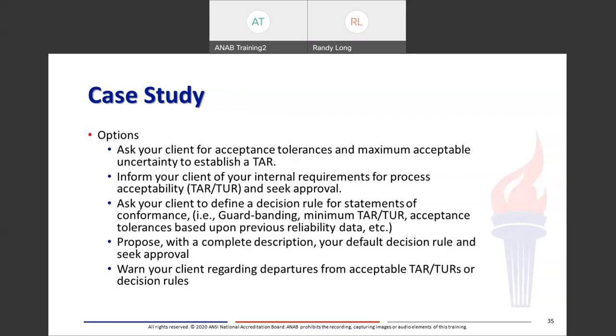Options: a calibration laboratory can ask a client for acceptance tolerance and maximum acceptable uncertainty to establish a test accuracy ratio. The laboratory could inform the client of internal requirements for process acceptability and seek the customer's approval. A calibration laboratory can ask the client to define a decision rule for statements of conformance — for instance, guard banding, minimum TAR, or acceptance tolerance based on previous reliability data. You should propose with a complete description your default decision rule and seek approval, and also warn your clients regarding departures from acceptable TARs, TURs, or decision rules.